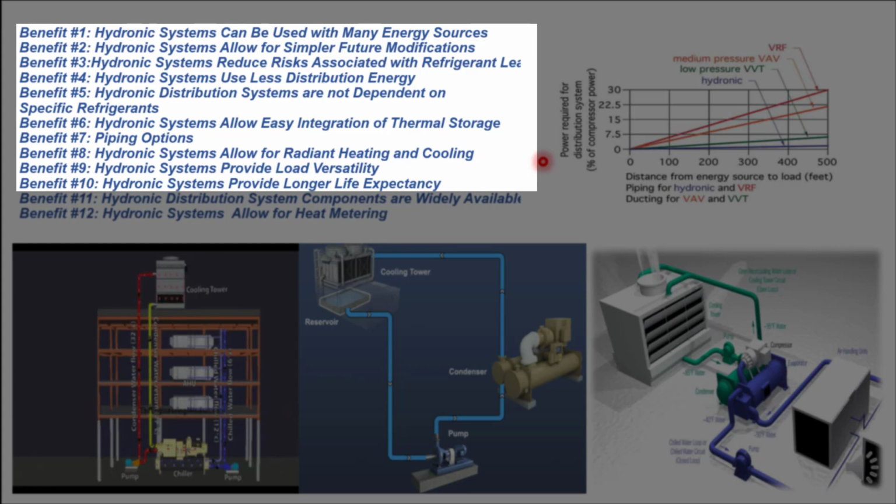They can share the load based on the most favorable operating conditions for each source. Likewise, many options exist as sources of chilled water for hydronic-based cooling systems. They include chillers and heat pumps operating on the standard vapor compression refrigeration cycle, as well as gas-fired absorption chillers, and even water drawn from large deep lakes, whereas VRV systems are solely sourced by electricity.